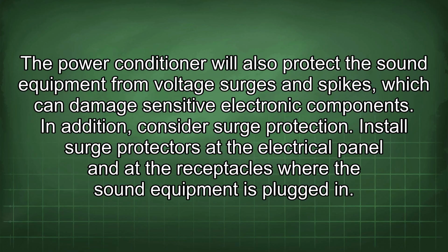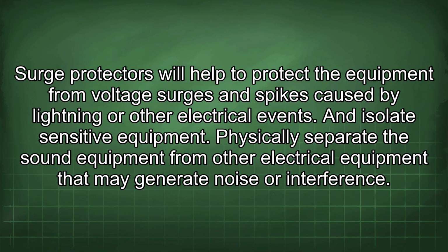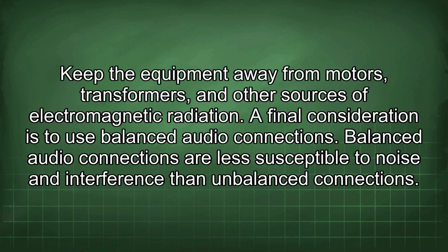In addition, consider surge protection. Install surge protectors at the electrical panel and at the receptacles where the sound equipment is plugged in. Surge protectors will help to protect the equipment from voltage surges and spikes caused by lightning or other electrical events. And isolate sensitive equipment. Physically separate the sound equipment from other electrical equipment that may generate noise or interference. Keep the equipment away from motors, transformers, and other sources of electromagnetic radiation.